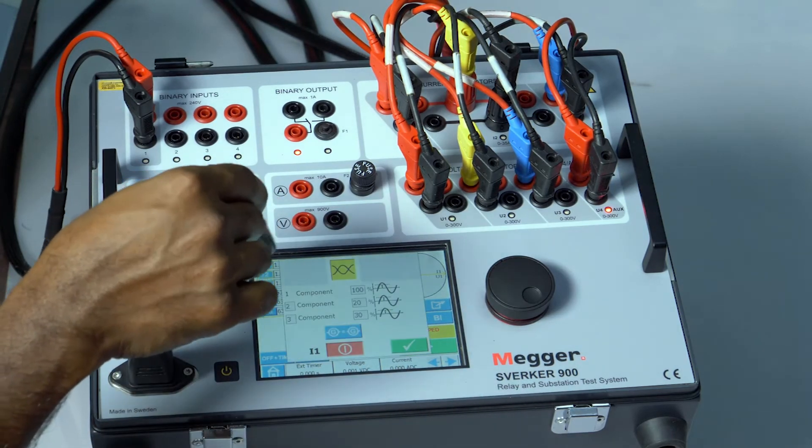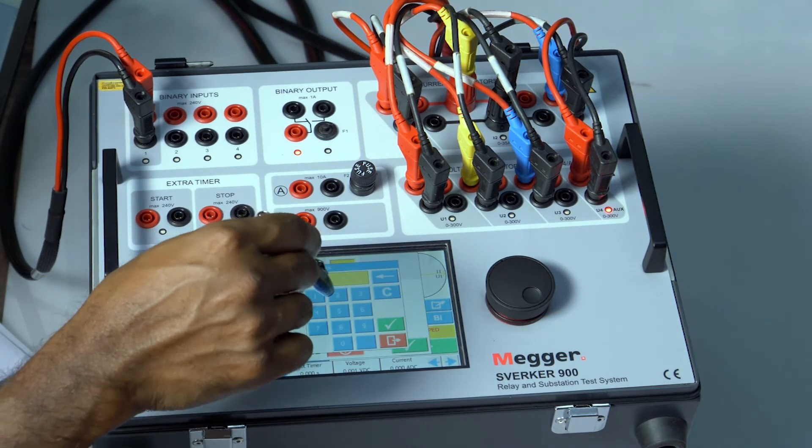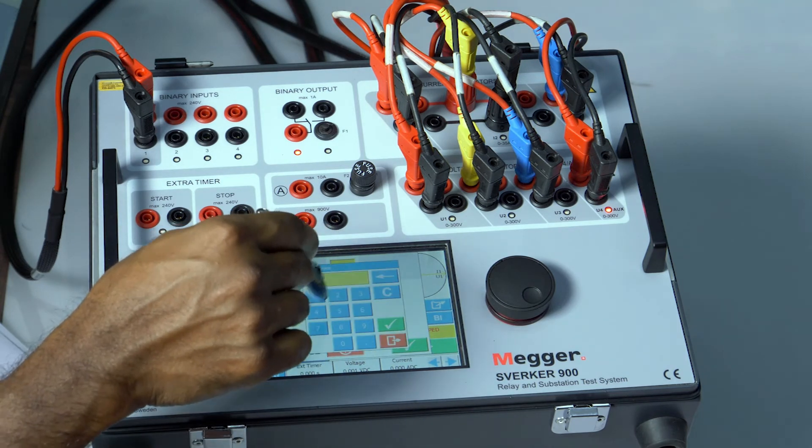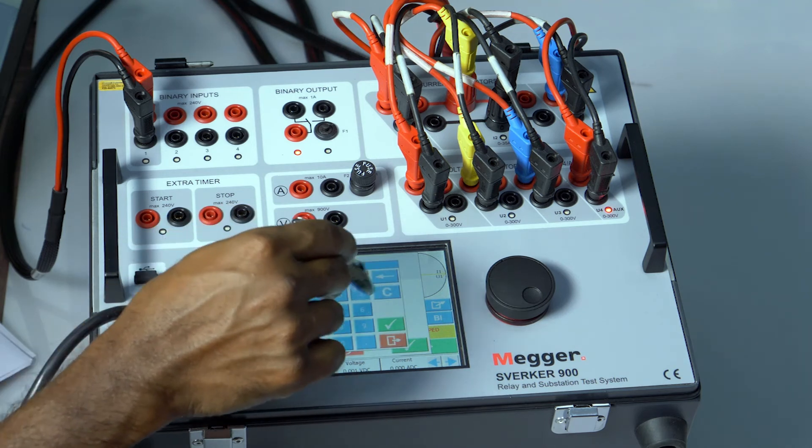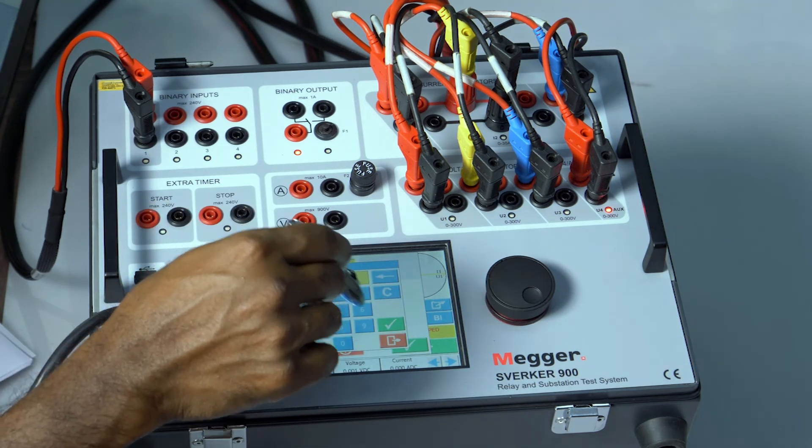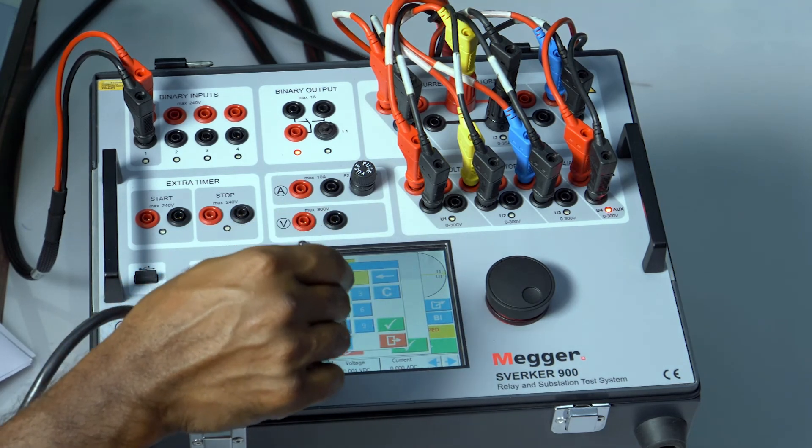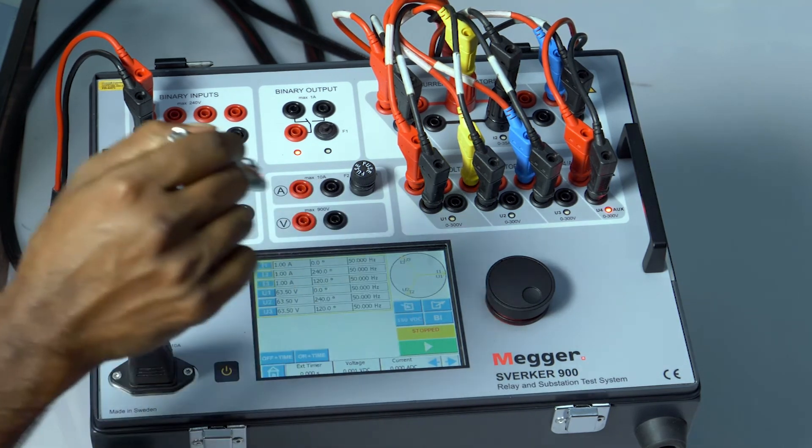If I remove this by pressing the I1 button, I am going to configure this for 3rd harmonic. Let's say 5th harmonic and 3rd harmonic here. So 25% of 3rd harmonic and 10% of 5th harmonic. And the fundamental component has 80%. Let me run this test.